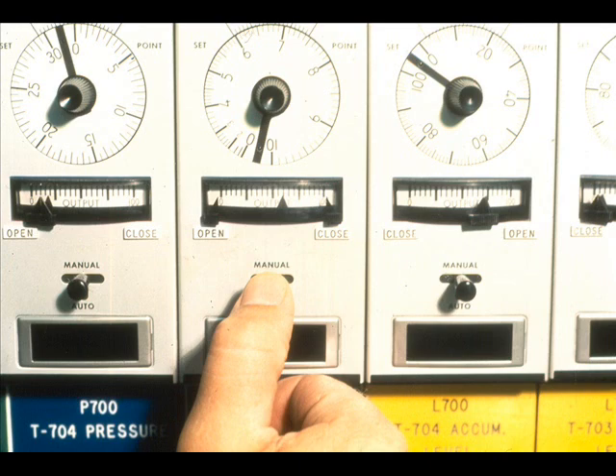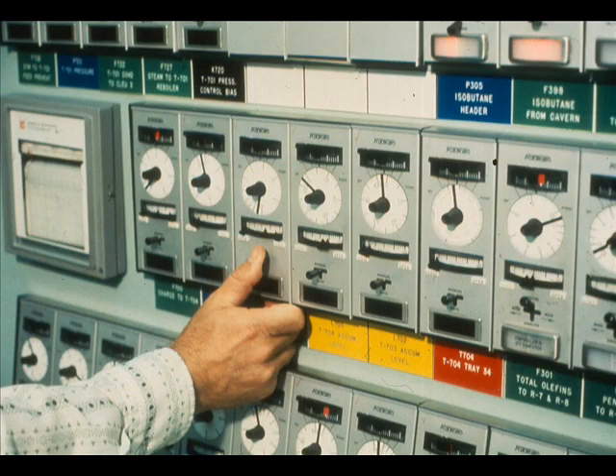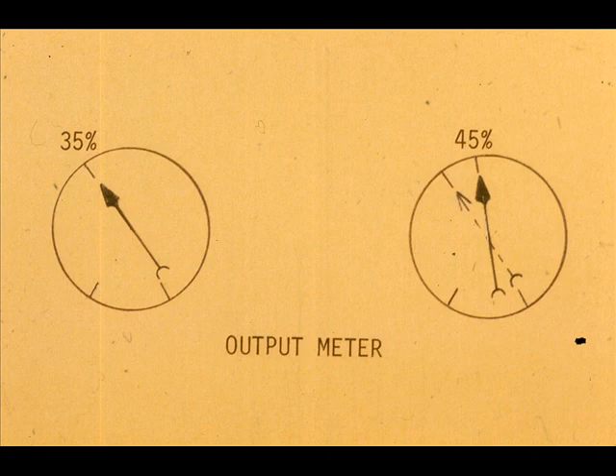First, put the controller on manual. Line out the process at some desired place on the chart and observe the percent of output to the control valve. Make a definite percent change in the controller output — this can be measured on the output meter. We will make a ten percent change; this is an arbitrary number. The smaller the percent change, the less upset to the process.